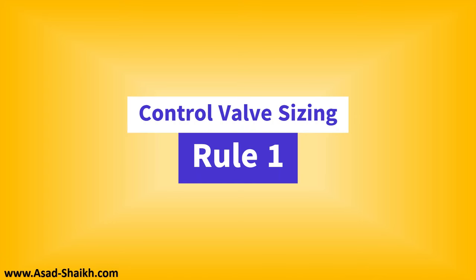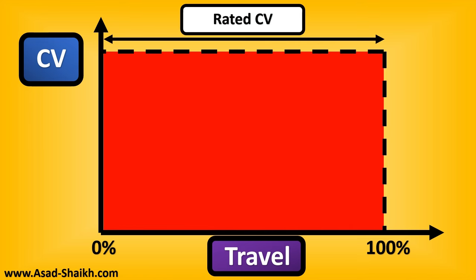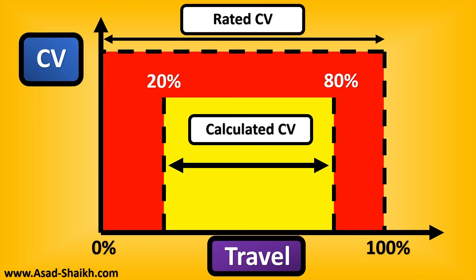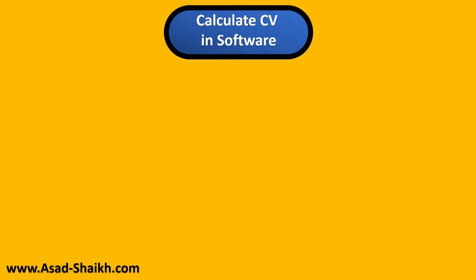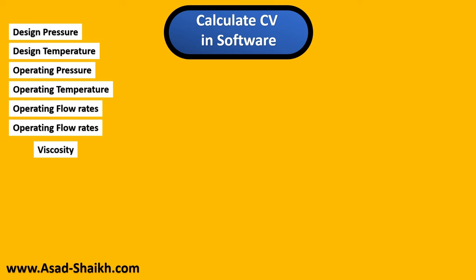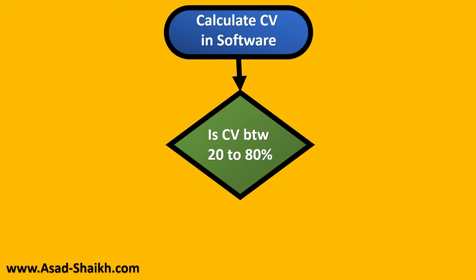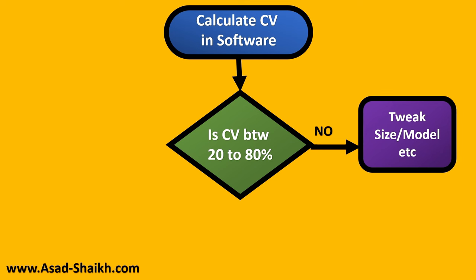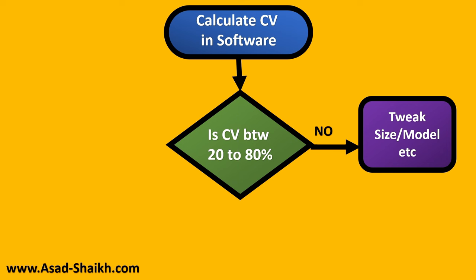This gives us the first rule of control valve sizing: in terms of capacity, the calculated CV must be within 20 to 80 percent of the rated CV. When you put all the process parameters in and get the CV at minimum, normal, and maximum conditions, those values should be within 20 to 80 percent of the rated CV. If not, you need to tweak the size or model. The valve should be at least one size less than the line, and it is preferred not to make the control valve too small.